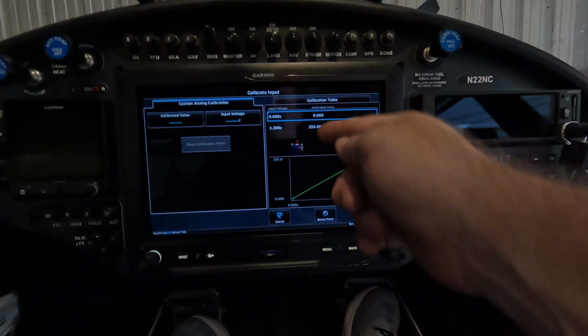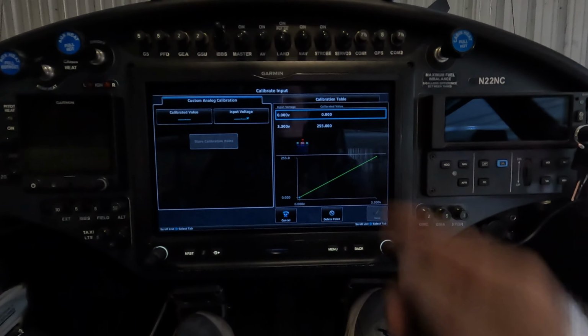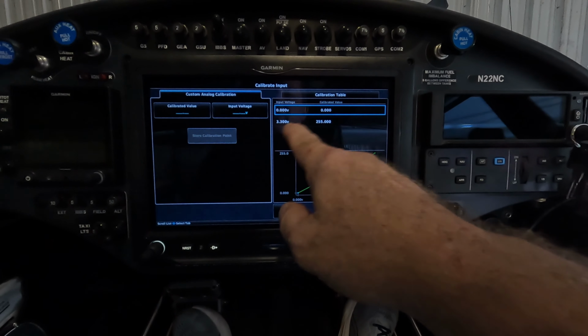You can see the default is 0 volts, is a calibrated 0 parts per million. And then your max value for 255 by default is 3.3 volts. Well, we need to change those.